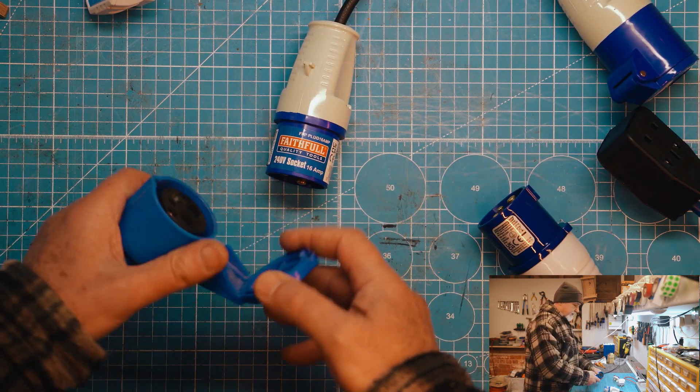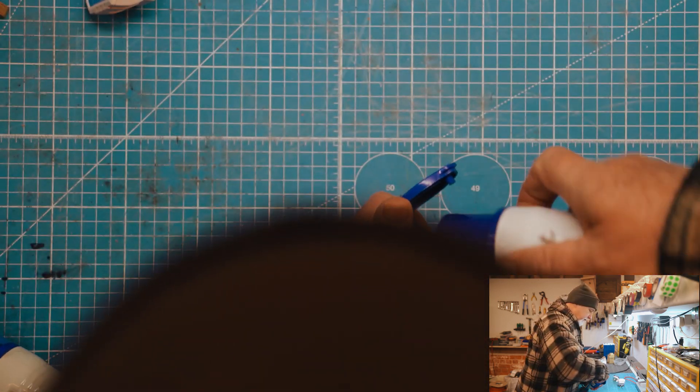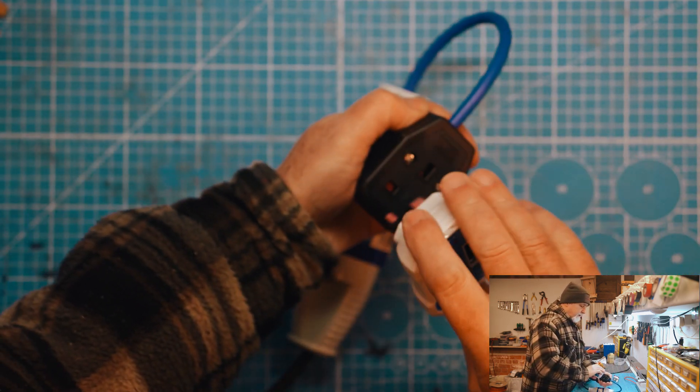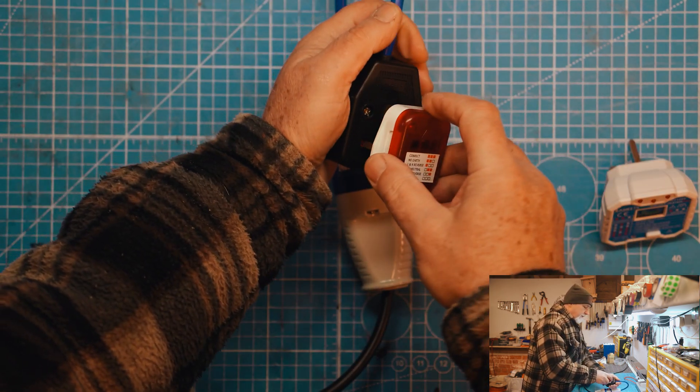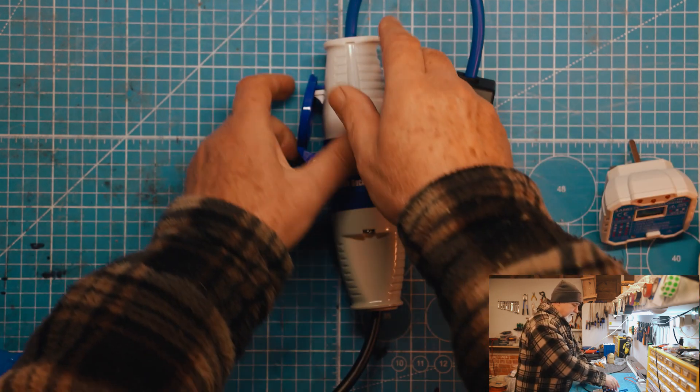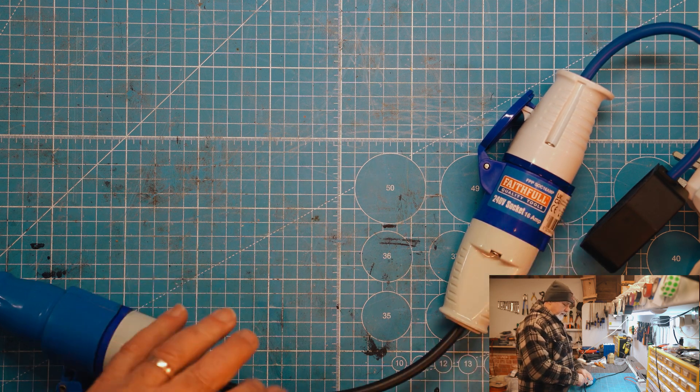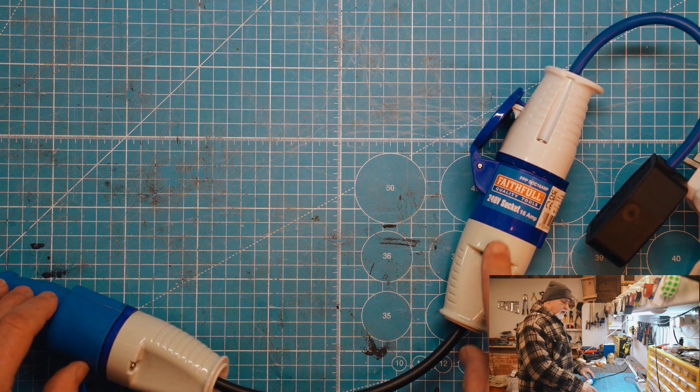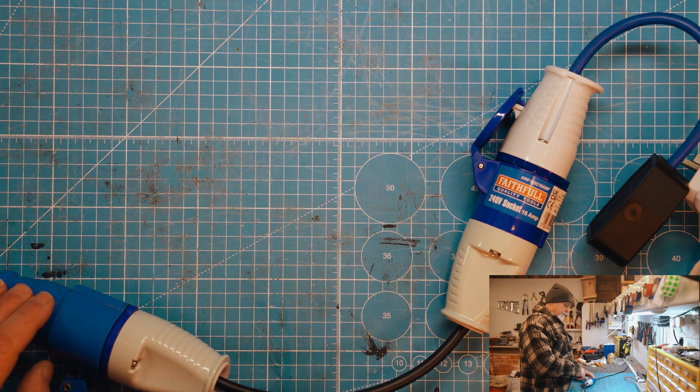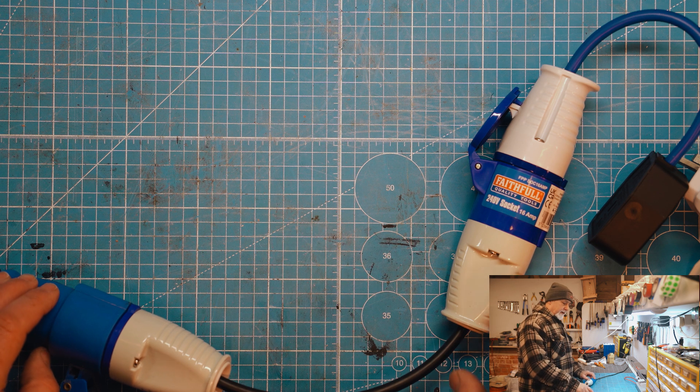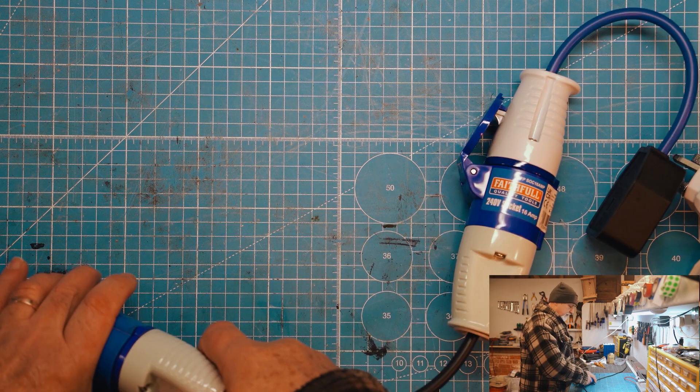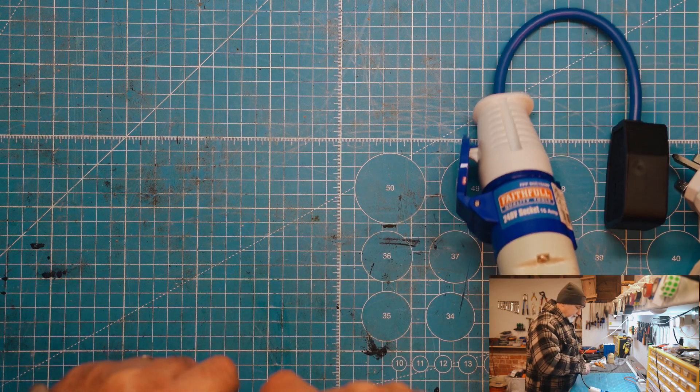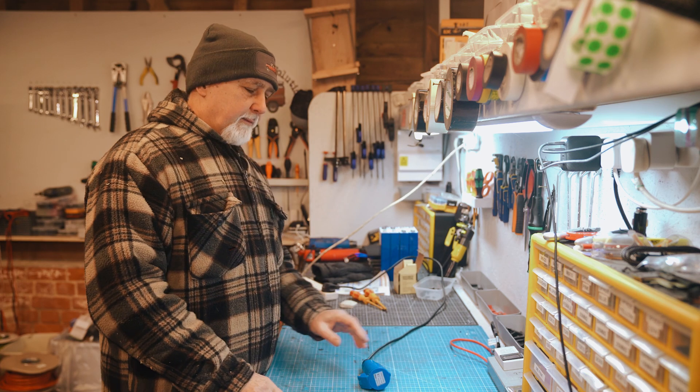So we've got it reversed here. This is a crossover that's going to re-reverse it so that it's actually correct. Getting quite busy with all of these plugs here. But then you can see, according to our one tester, we're back down to the two, which is correct. And look at this other one, we're back to three, which is correct. That's what we want to see. So a simple little device like this doesn't take up much room, just a plug and a socket and a very short length. I would do it really short and I would label it very, very distinctly. Maybe put some red Xs so that you know it's crossed over and even put a label on so that you absolutely know without a doubt it's crossed over. Just make sure that you label it really well so that if somebody else was to get hold of it, they wouldn't assume that it's just an extension.